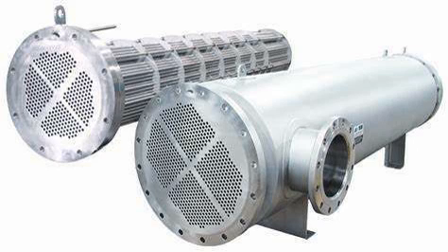Plate heat exchangers also differ in the types of plates that are used, and in the configurations of those plates. Some plates may be stamped with chevron, dimpled, or other patterns, where others may have machine fins and/or grooves. When compared to shell and tube exchangers, the stacked plate arrangement typically has lower volume and cost. Another difference between the two is that plate exchangers typically serve low to medium pressure fluids, compared to medium and high pressures of shell and tube.